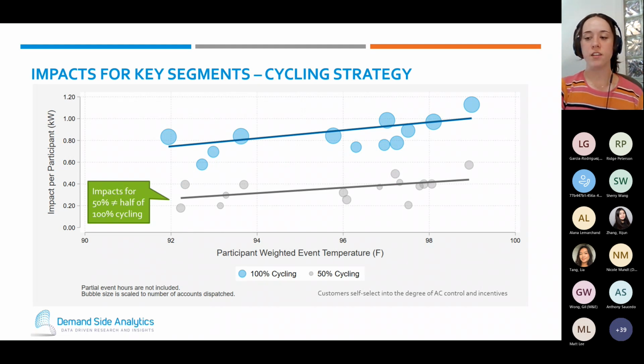This starts to look at it by cycling strategy. I've been talking about the 100% and the 50% cycling groups, and you can see it broken down — the same impact per participant and temperature trend, but split between 50% and 100% cycling. As you can see, the 50% cycling on a straight impact-per-participant level is going to reduce demand less, because those participants are not cutting their AC nearly as much.